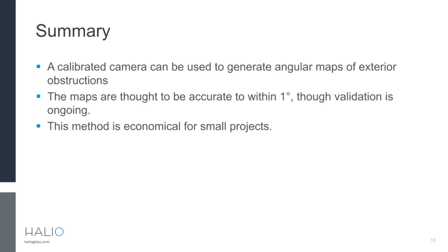In summary, a calibrated camera can be used to generate angular maps of obstructions. The maps are thought to be accurate within one degree, though more validation is ongoing. We need to test sun positions over a wider area of the map. At about five minutes per obstruction map, this method is economical for small projects. For large projects, it might be used to validate a ray-traced map in situ after a building is built.